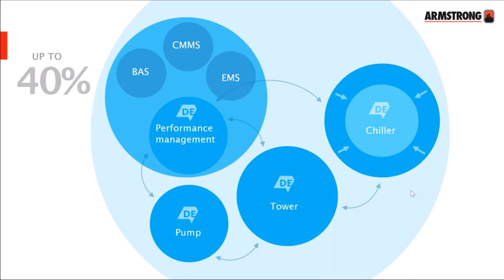In practice, we see the plant systems are often oversized from day one, and this will come as no surprise to anyone on this webinar. In an upgrade, the tendency is to replace like for like capacity, 500 kilowatt chiller for 500 kilowatt chiller, and so on, while the building demands have changed over time since that original chiller or boiler was installed.